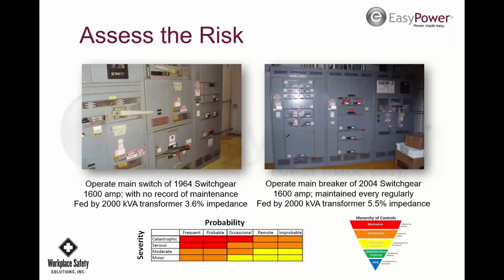So what I've done in the past, I've run into that quite a bit actually, is I will do it in stages. So this year we'll budget to do the utility and the main switchgear, and then next year we'll go to the panel level. And the following year we may go to the control panel and disconnect level, depending on what it is. So just in a tier system, but at least it gives you a little bit of an idea on the highest level stuff what your PPE needs to be.